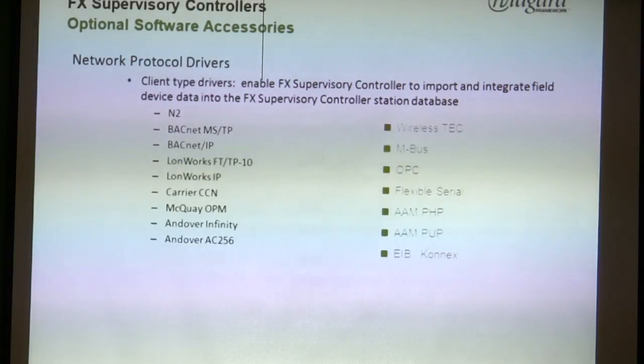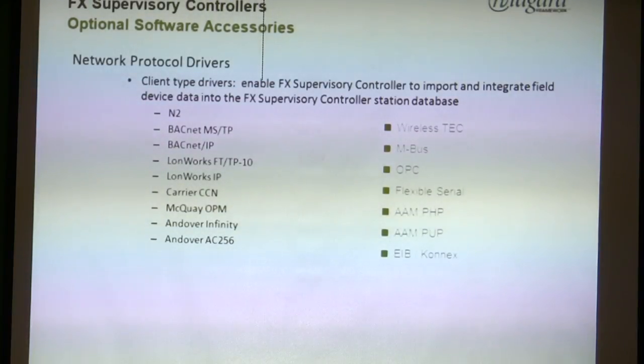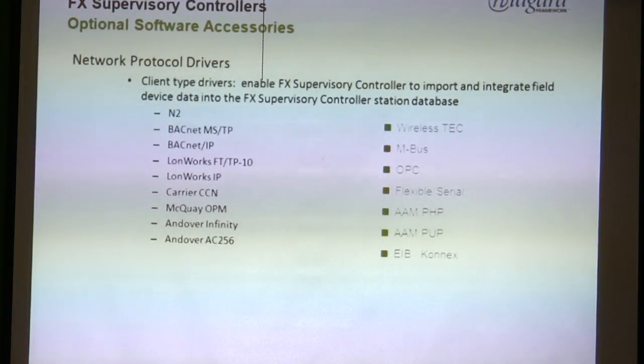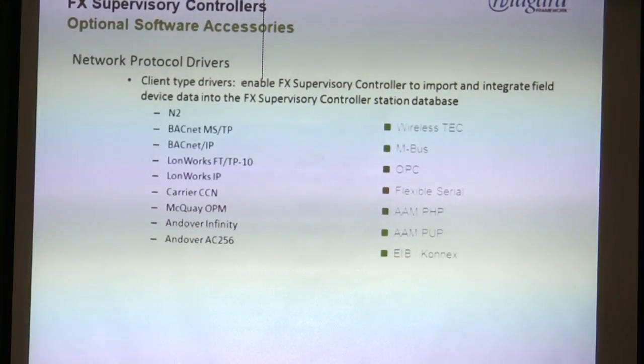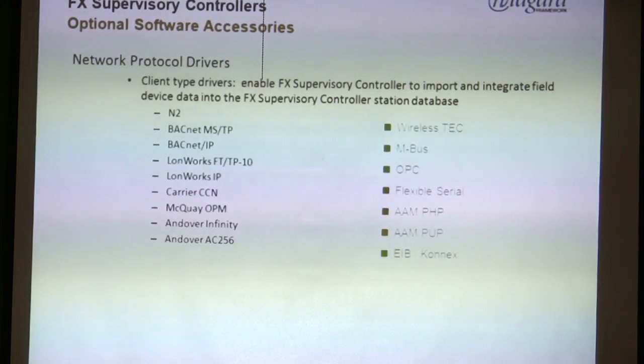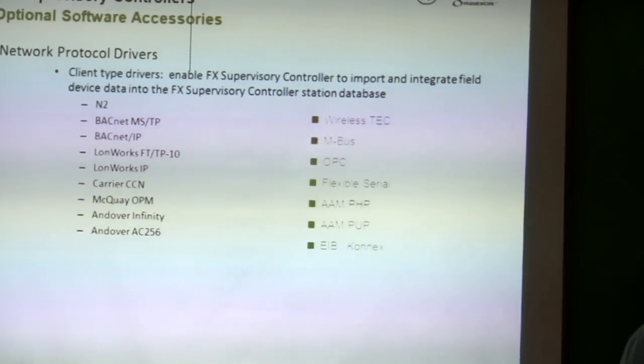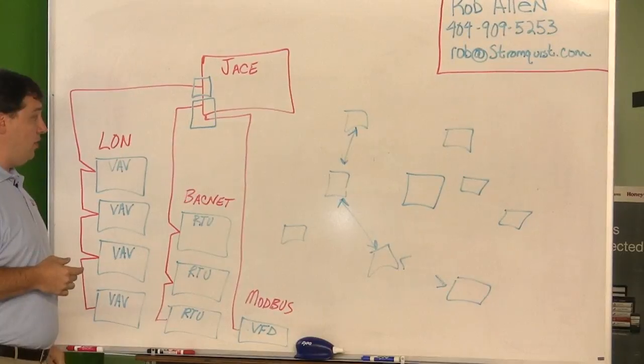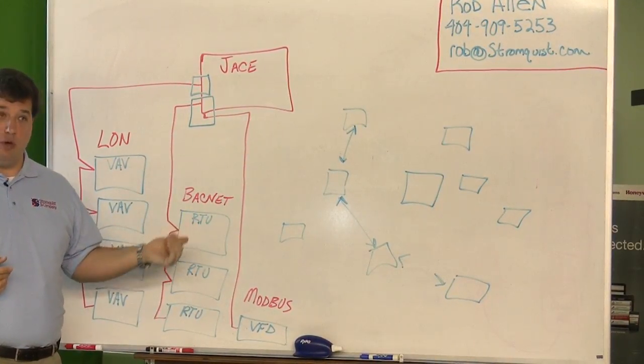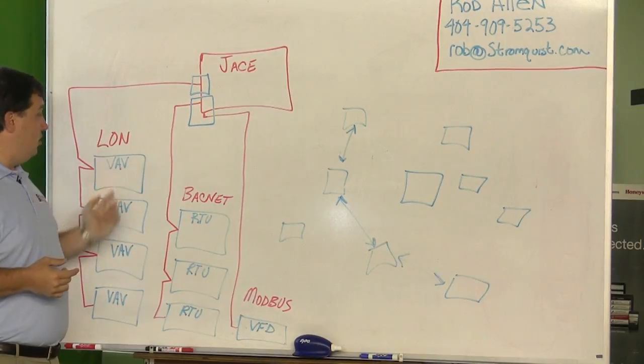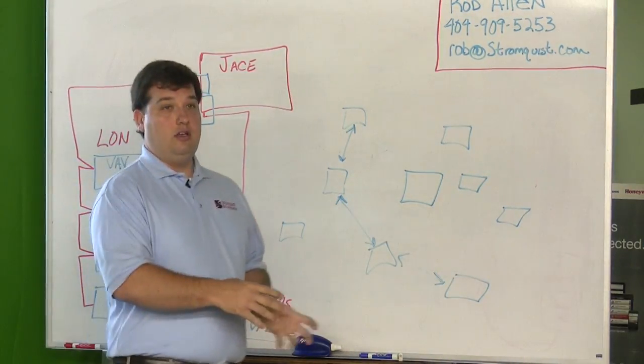Everyone knows that when you plug a USB mouse into a computer for the first time, Windows makes that sound and installs a driver. Same thing with the Jace — you need drivers. If you're going to do a LonWorks, BACnet, or Modbus system, you need the communication card hardware and also the corresponding software driver. That driver is what allows those controllers to talk to the Jace — hardware side and software side.